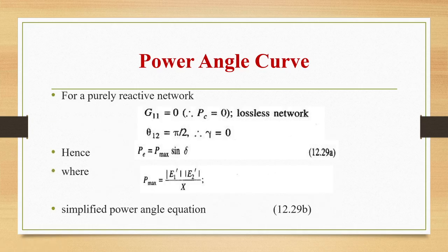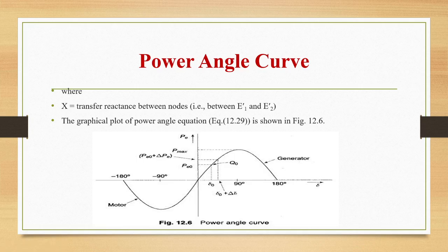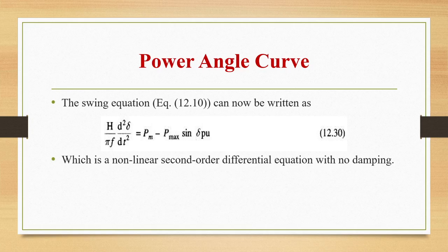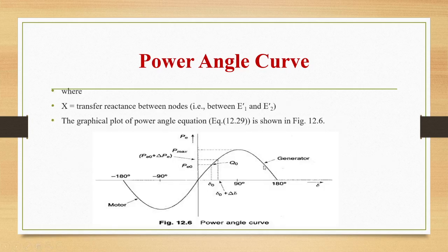The swing equation thus becomes (H/πf)·d²δ/dt² = Pm − Pmax·sin(δ) per unit, which is a nonlinear second-order differential equation with no damping. The power angle curve plots Pe on the y-axis versus δ on the x-axis. For a generator, the curve is in the positive region; for a motor, in the negative region. Key operating points such as Pe0, δ0, and δ0 + Δδ are identified on the curve.